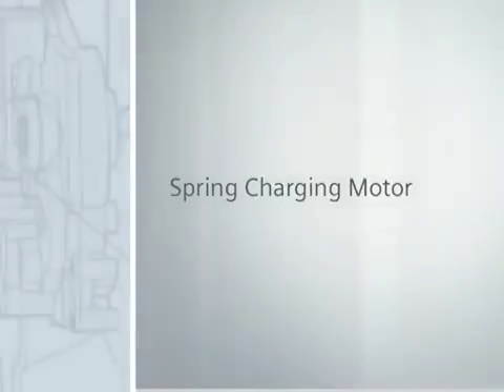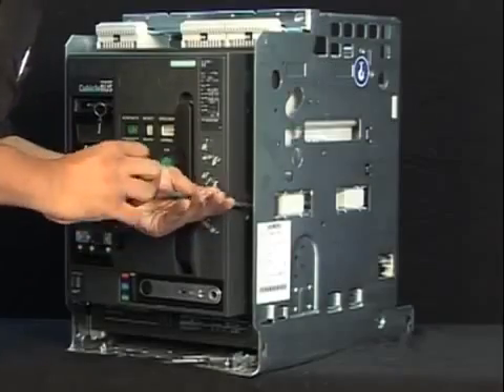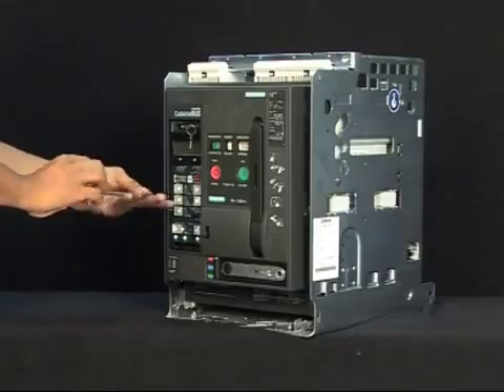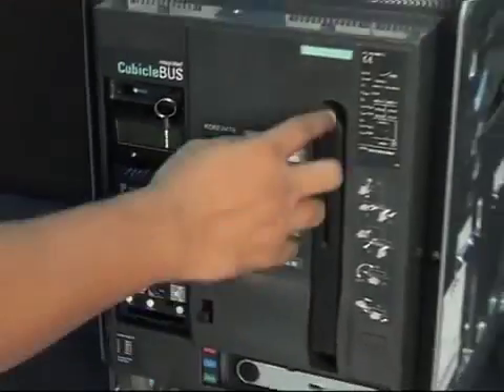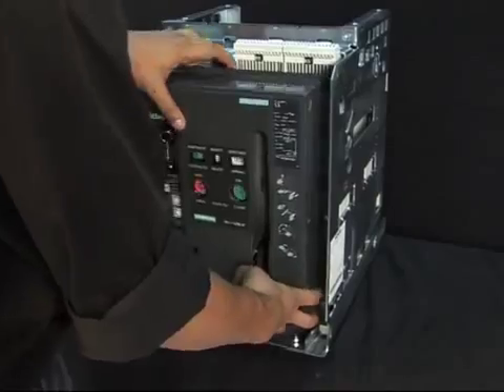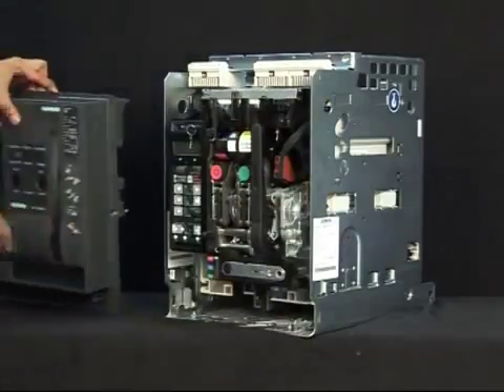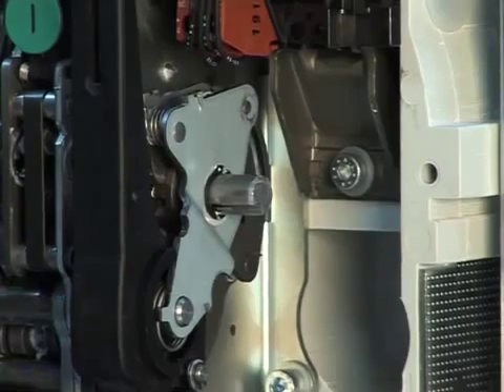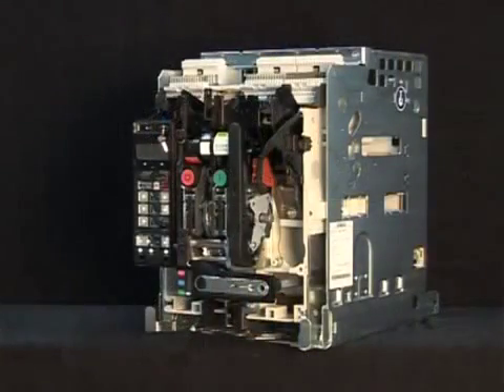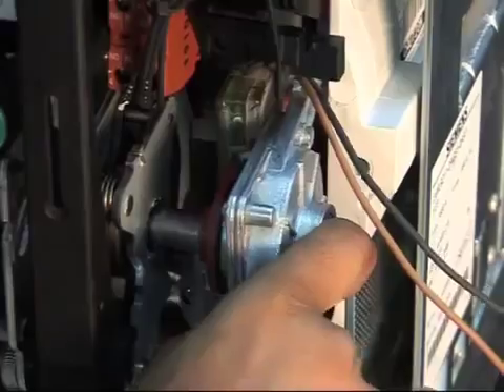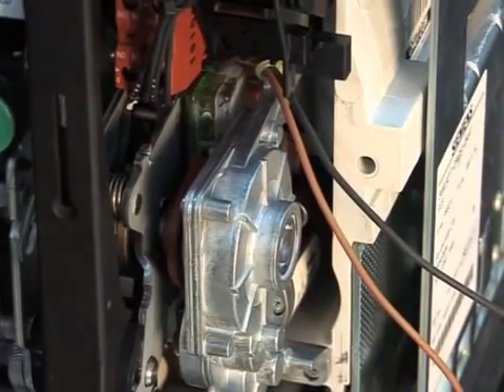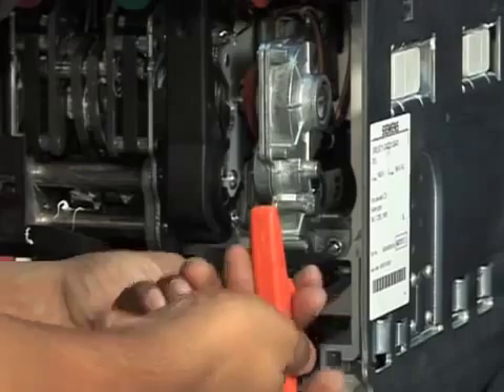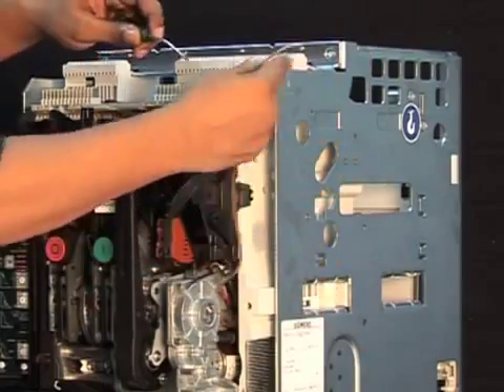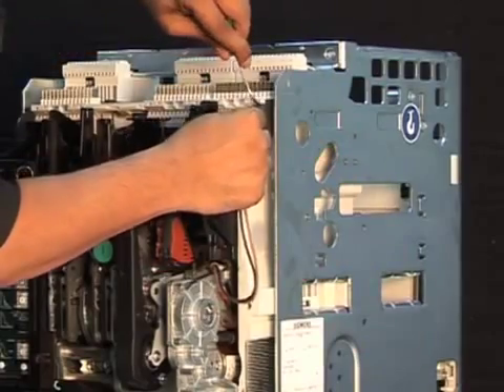First, we'll display the process of fixing the spring charging motor. After undoing the screws, you have to swing down the charging lever to take out the front panel to expose the internal compartment of the charging motor. On the left-hand side wall, you will find a shaft called spline shaft of the manual operating mechanism. The motorized mechanism is inserted in its slot and fitted on the spline shaft. The single screw is then fixed and the cables are tied neatly to connect to the auxiliary screw connectors.